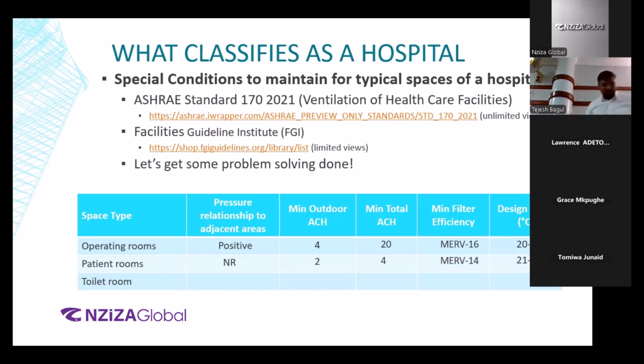Anyone from the... okay, I've already displayed it. But patient room is NR. We'll talk about NR in a moment. The minimum outdoor air changes for patient rooms is 2. Minimum total air changes per hour for a patient room is 4. MERV rating is 14, and the design temperature is 21 to 24 degrees centigrade. Is this what all of you got?